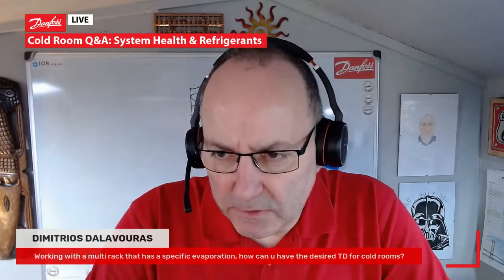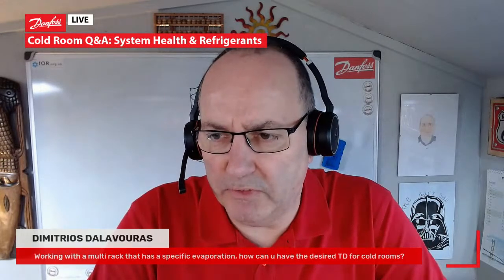Okay. So, if you work with a multi-rack that has a specific evaporating temperature, for example, -8 degrees C, how can you have the desired delta T for different cold rooms? For example, the DT would be 8K for the meat cold room on 0C, but for the vegetable cold room on +5. Yeah, the simplest way is to have our rack.